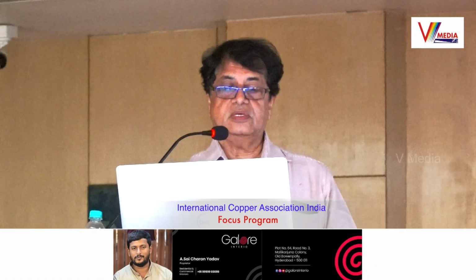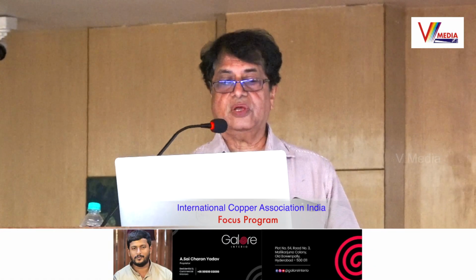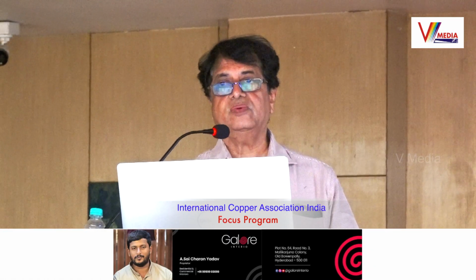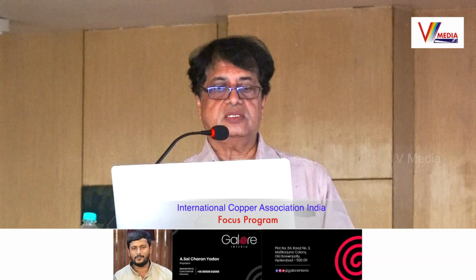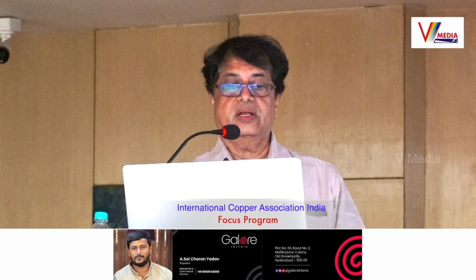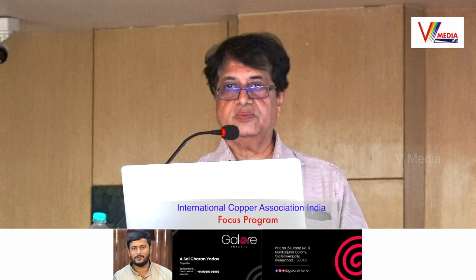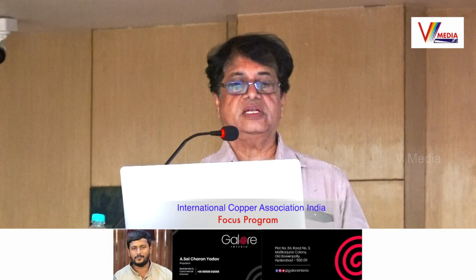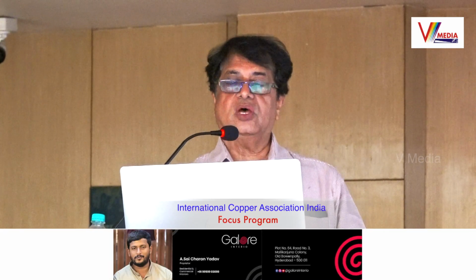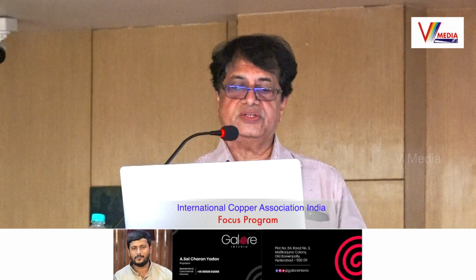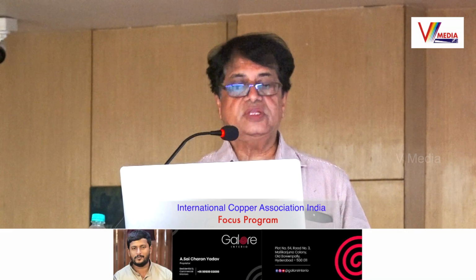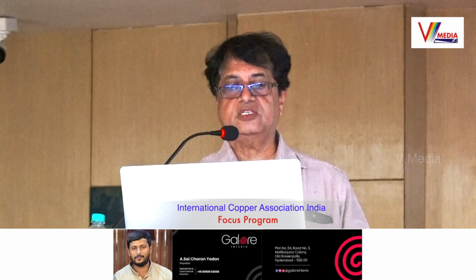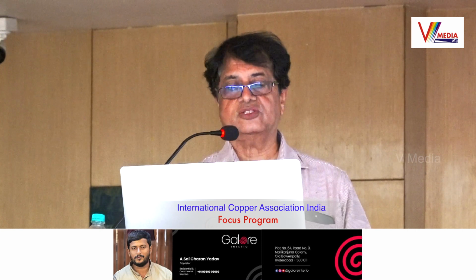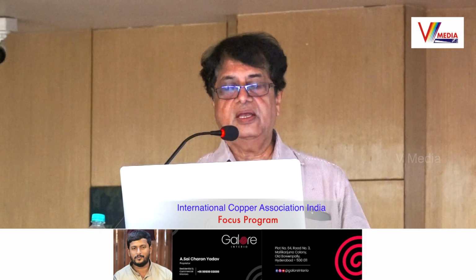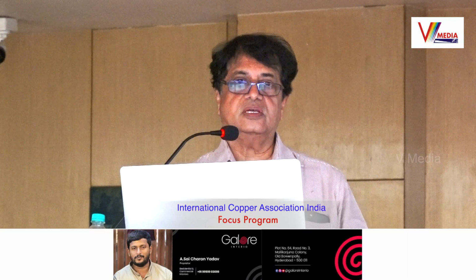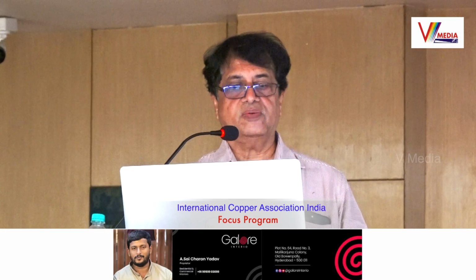It has been mentioned that if you are going for such a type of transformer, the oil which you use should be of K class. The K class oil has a 300-degree fire point, and it is called esters. Esters come in two different types, synthetic ester and natural ester. Both of these oils are allowed under different conditions. So this is an important point which we need to consider. There has to be sufficient space. If you are going to install an oil-filled transformer, it should be away from the building, and the liquid which is going to be used, in consultation with the electrical designer, should be of K class.